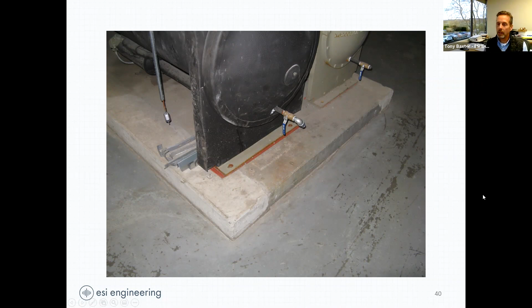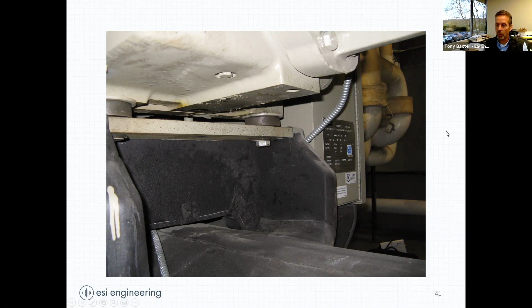One of the things we always get is, yep, well, hey, all the compressors and everything in this equipment are isolated. Yeah, here's the isolation. It's a really hard rubber or urethane isolator with a bolt going through it. And I mean, how thin is that rubber? This is stiff stuff. It doesn't provide much for vibration isolation and for noise control. So what we designed was a steel structure that fit around the chiller with air mounts. So of course we had to be able to get it in the elevator to get it up to this point. So it came in pieces, everything bolted together, and then we put the air mounts in.